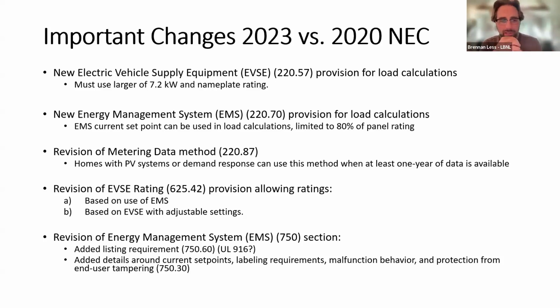We also have a revision to the EVSE ratings in 625.42, kind of explicitly letting us derate those appliances based on whether we're using an energy management system, or some of our EVSE have adjustable settings, where you could set it to a lower value and then take credit for that in the electrical code.